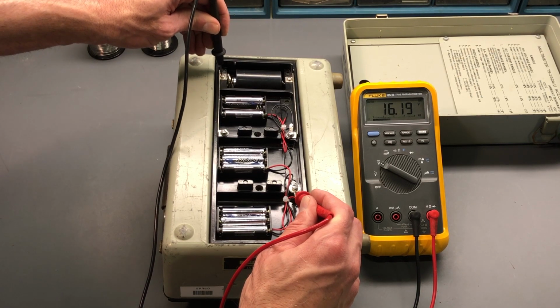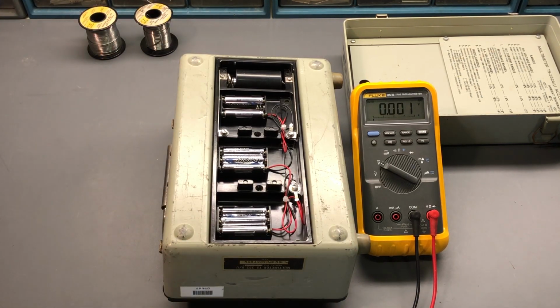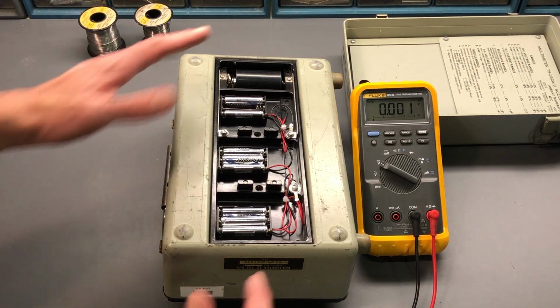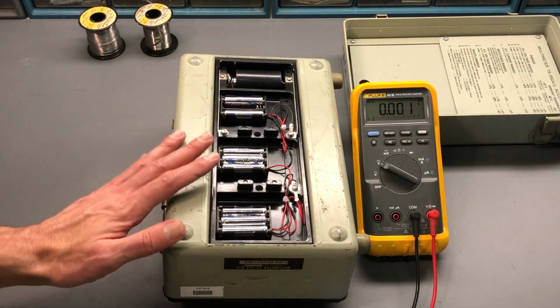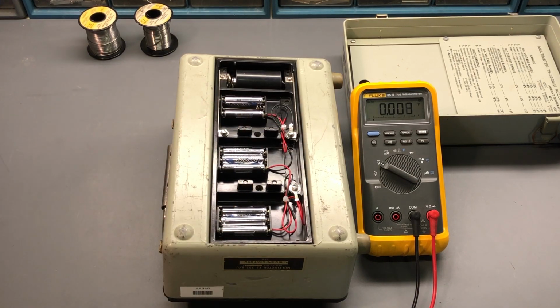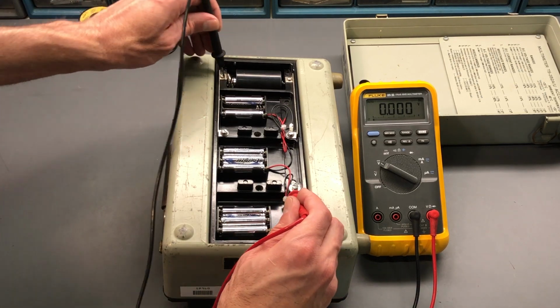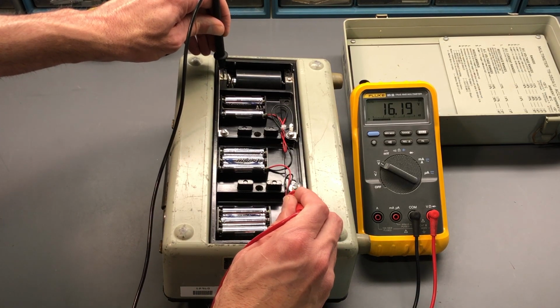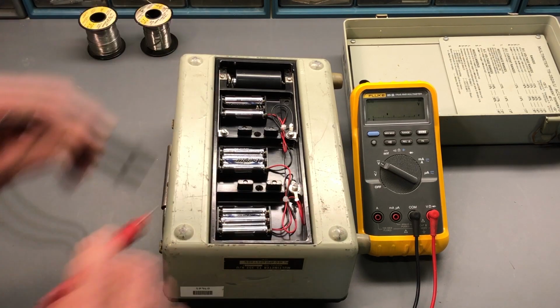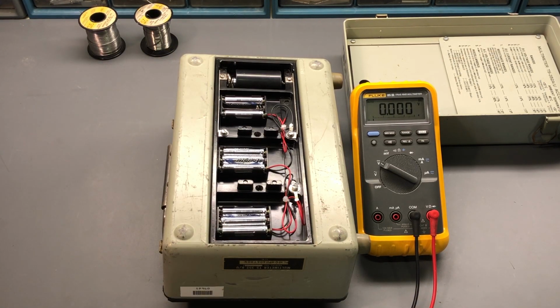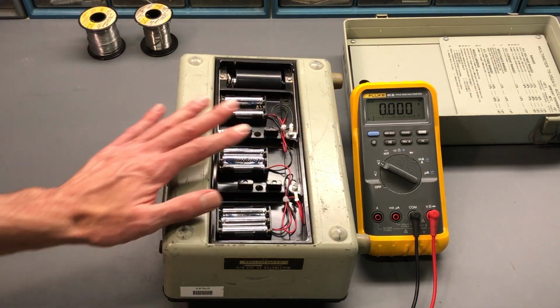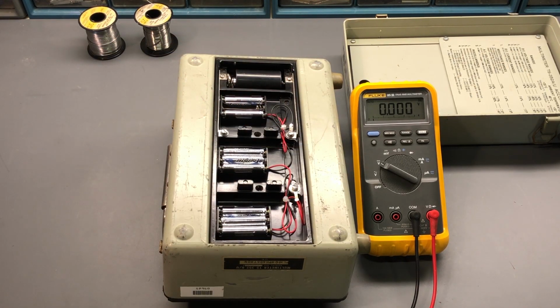So that's the total voltage, 16.19, and that's used on that highest ohms range. Now remember that the total voltage the meter can withstand and still zero out on the highest ohm range is 16.9. So again, we have 16.19, and 16.9 is the highest, so no problems there. The meter shouldn't have any issues whatsoever. The lowest that this can fall to and still be able to zero out is 13.7. So that's the usable range that the meter is able to tolerate and zero on the ohms setting.